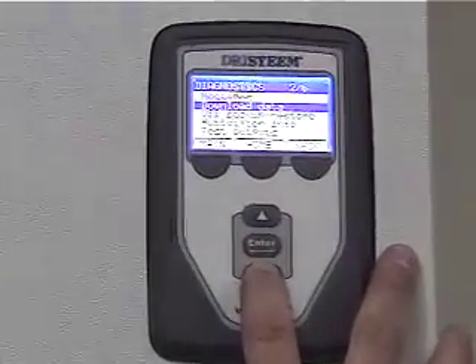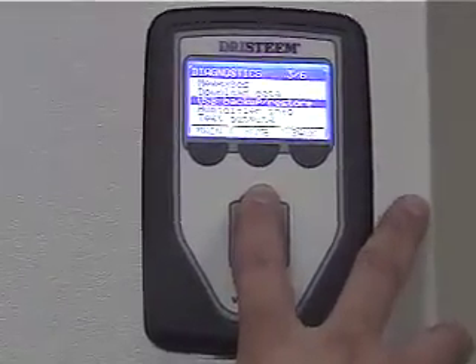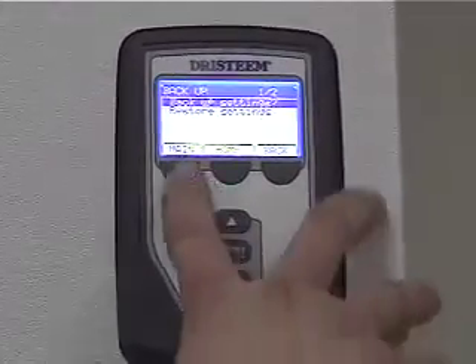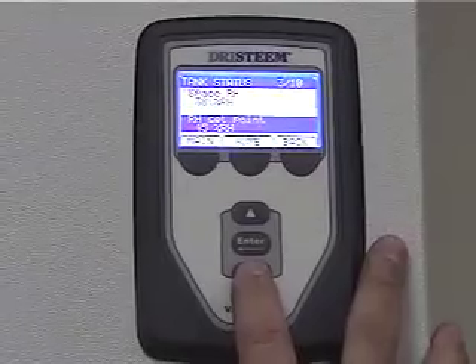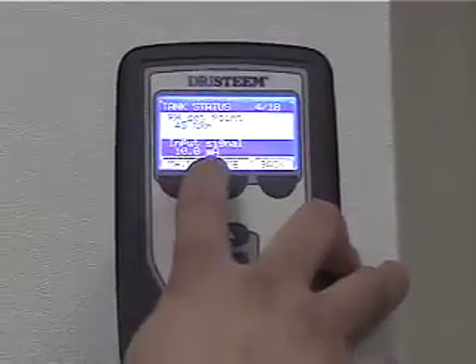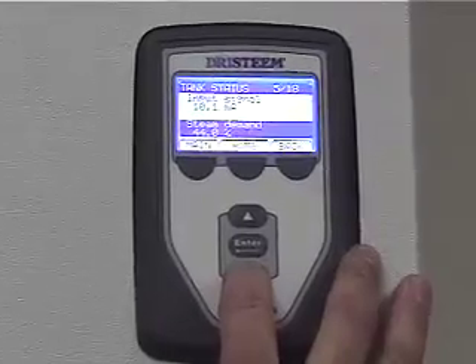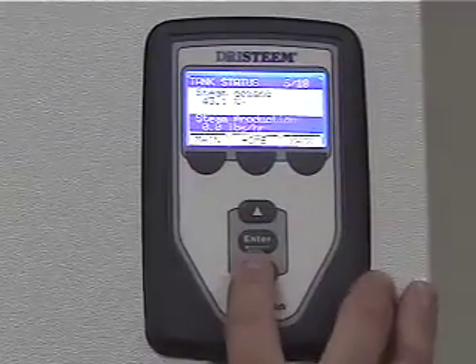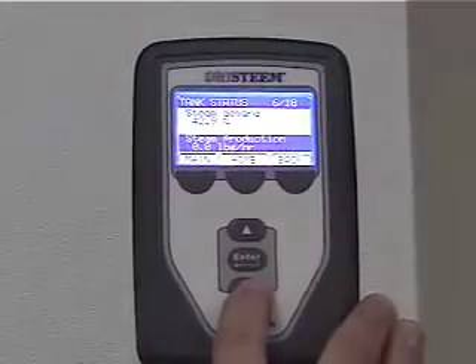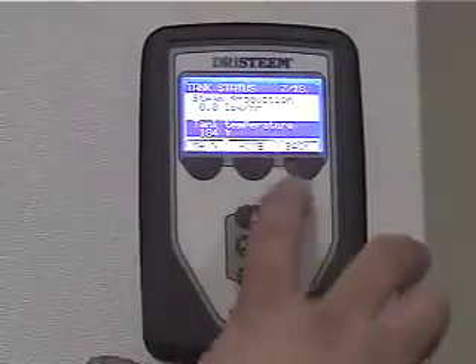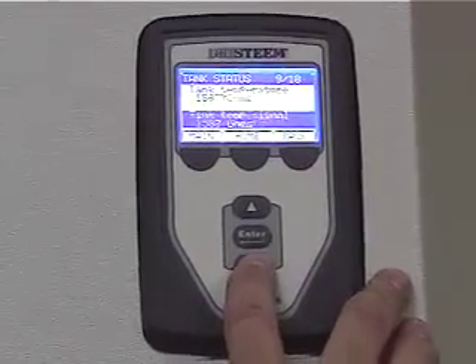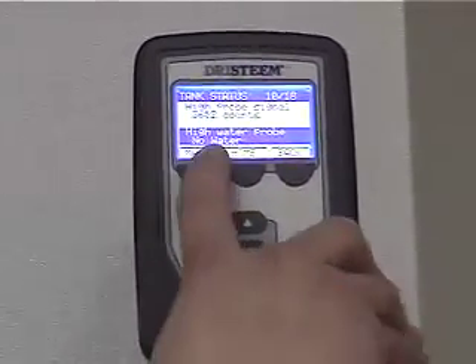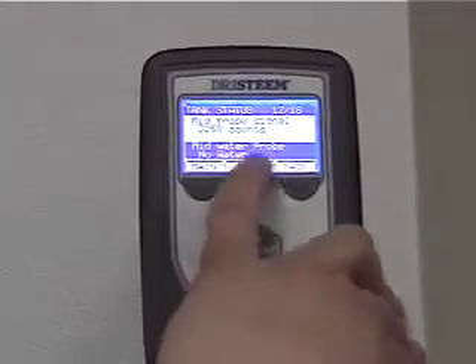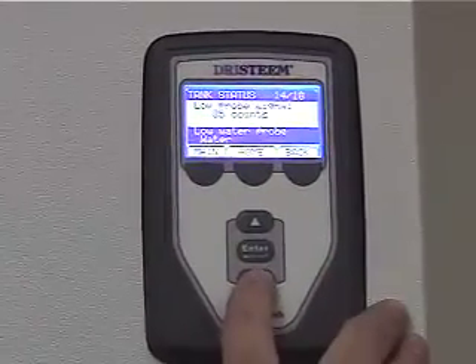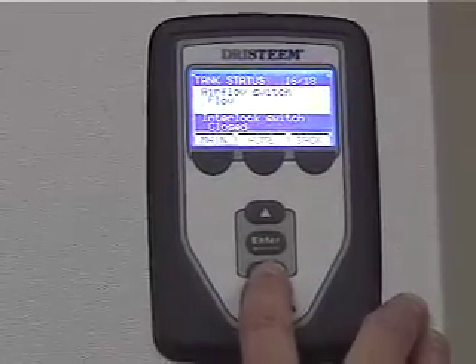We can come in here and start seeing the diagnostics again. I think it's in tank status. We've got a 10 milliamp signal right now. The steam demand is 40. That's what the demand is right now. What it's producing right now is 0 because we haven't started flashing. Our tank temperature, our tank ohm signal: our high probe has no water on it yet, our mid probe has no water on it yet, our low probe has water on it. Our airflow is good. Our interlock switch is closed.